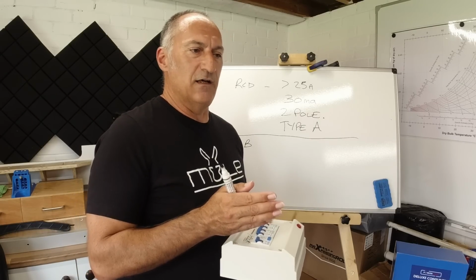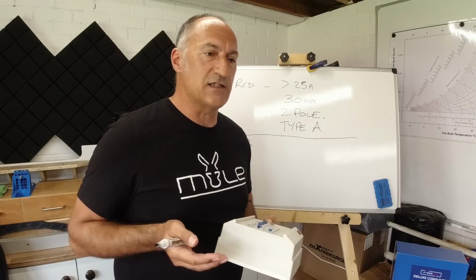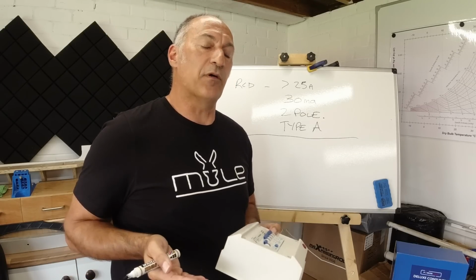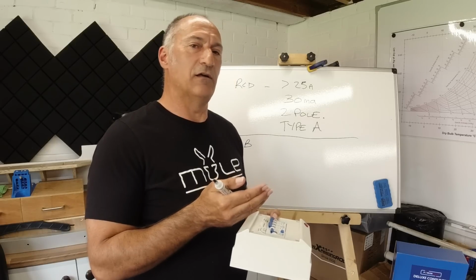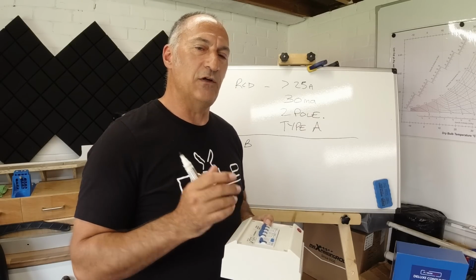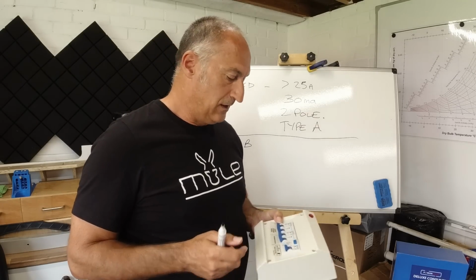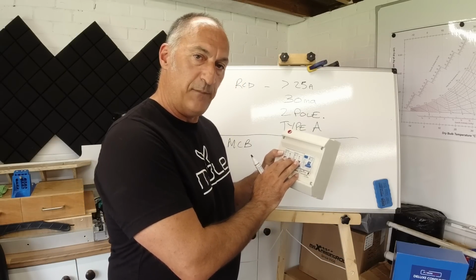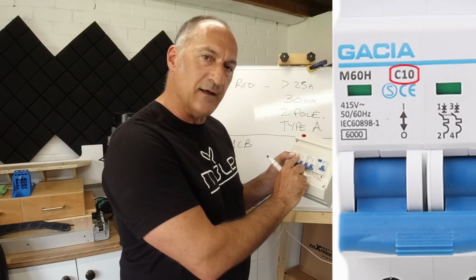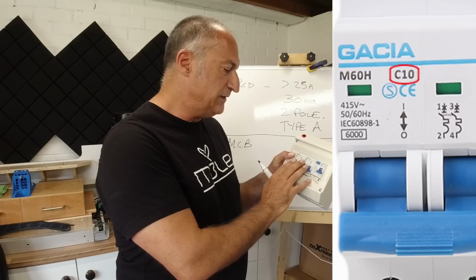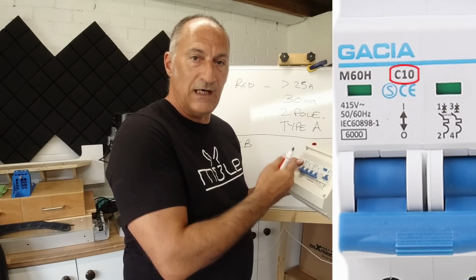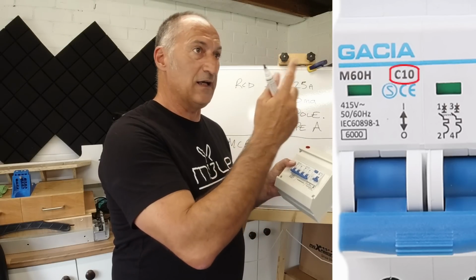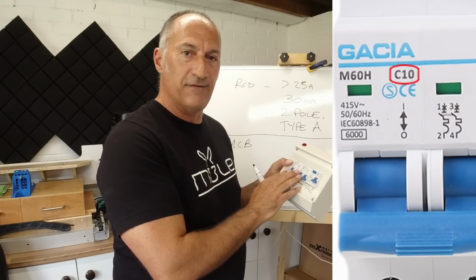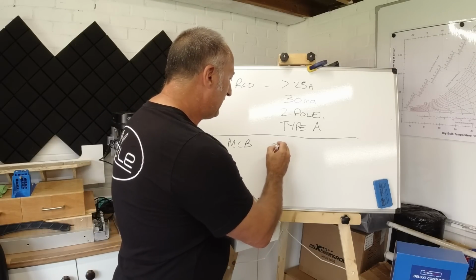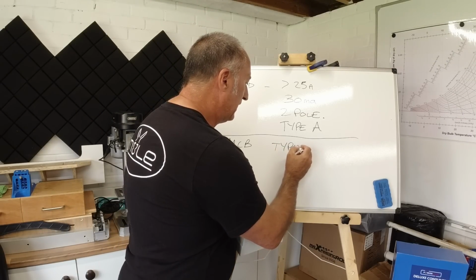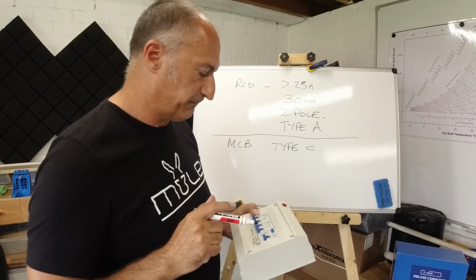For really basic circuits and a lot of domestic circuits, like lighting circuits, they're on a type B breaker, because you haven't got that initial current rush when you turn the lights on, so you need them to act fairly quickly. This particular consumer unit that I've purchased comes with a type C breaker, so it will cover you for normal loads and for motor type loads or anything with a large starting current, like a roof fan or water pump. So our MCBs typically for our camper van will be a type C MCB.